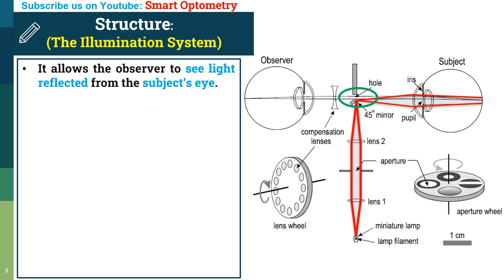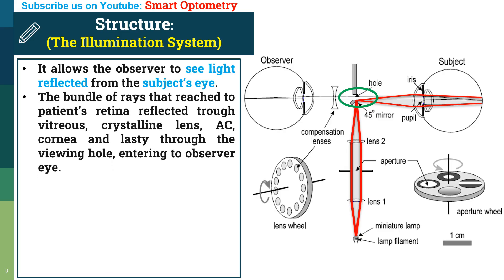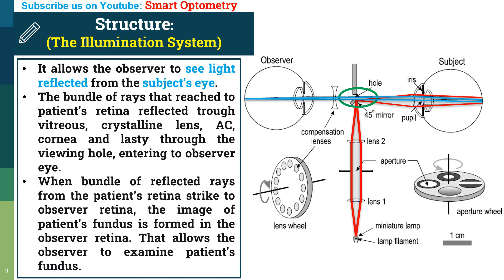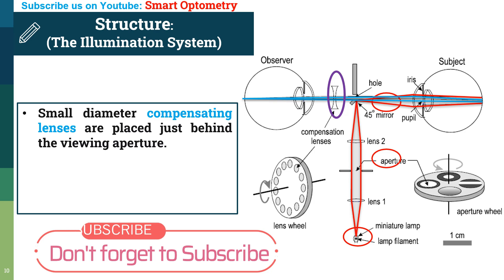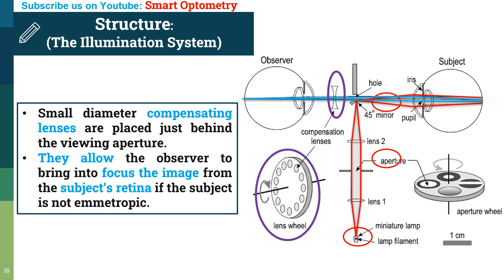The viewing system allows the observer to see light reflected from the subject's eye. The bundle of rays that reach the patient's retina are reflected back through the vitreous, crystalline lens, anterior chamber, cornea, and lastly through the viewing hole into the observer's eye. When the bundle of reflected rays from the patient's retina strikes the observer's retina, an image of the patient's fundus is formed, allowing the observer to examine it. Small diameter compensating lenses placed just behind the viewing aperture allow the observer to bring into focus the image from the subject's retina if the subject is not emmetropic.